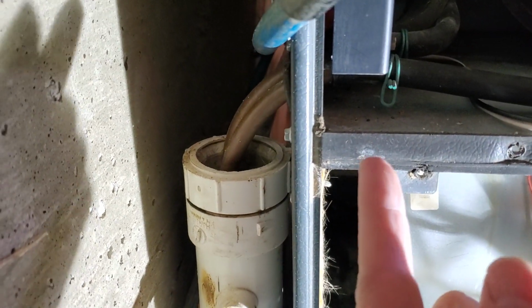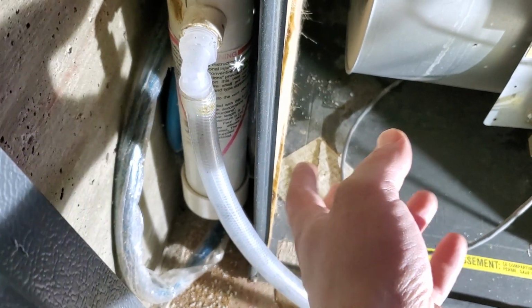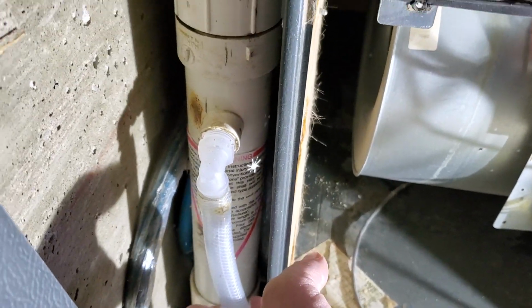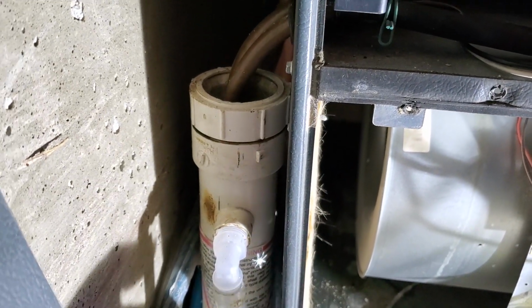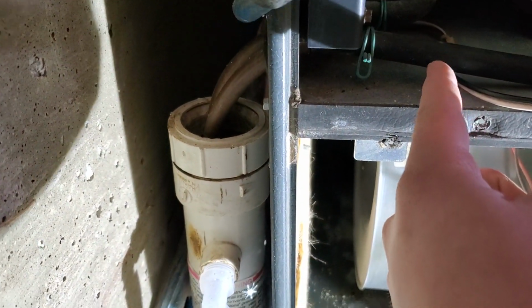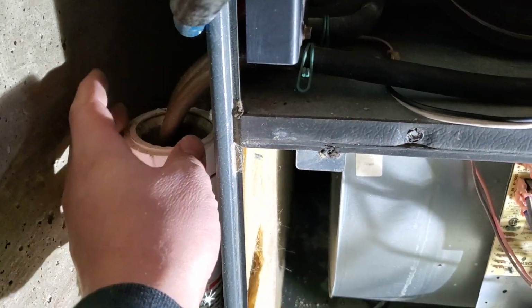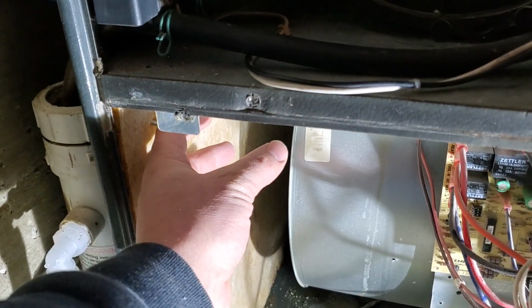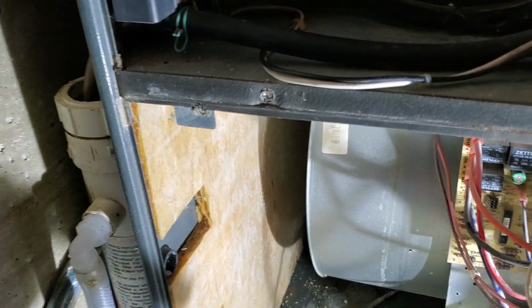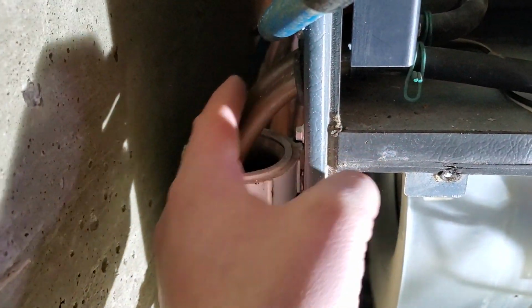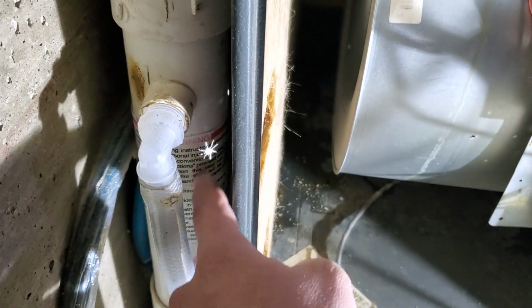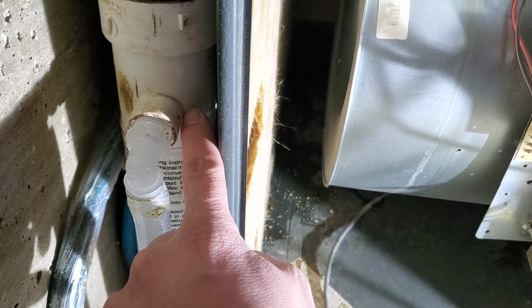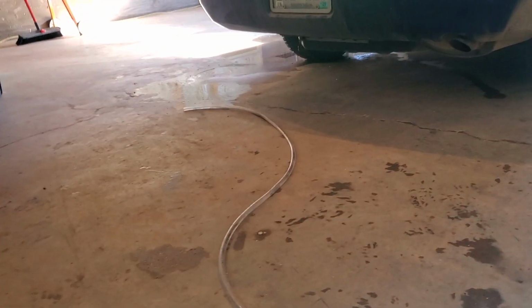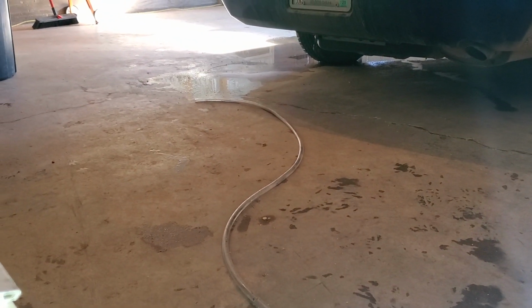Now this is a modified trap. This isn't the original one that was on here because the original one got broken off and lost somewhere. But in any case, it's very similar. Usually this trap will be internal, so you'll have some kind of a trap inside of here with one pipe coming out of it. But in this case, we have it on the outside. So these two copper pipes go down into this trap. They're down in the water, and then once the water reaches this level, it runs out our drain tube over towards the floor drain.